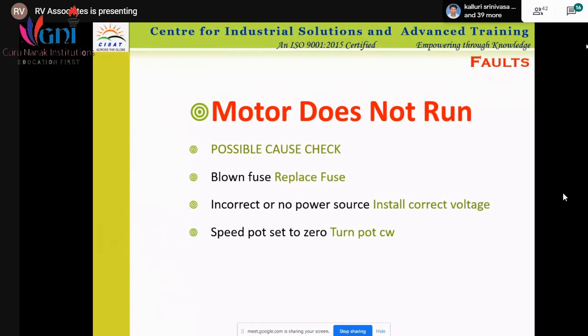and suppose an electrical drive is there, check the enable/disable parameter for the motor. We should know what parameters are needed just to run the motor. If not, the motor will not start. Last point, like the speed pot set to 0, turn the pot clockwise. You may say that it's okay, the motor started, but it is not enabled.